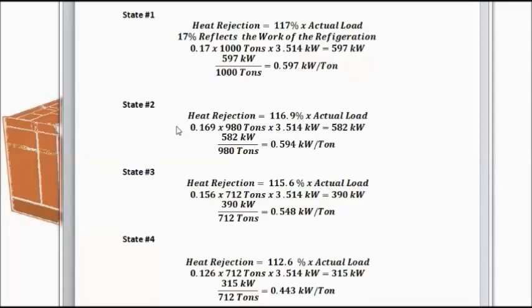And in state 2, we can make the same calculation. And we come out with 0.594 kW per ton. And since this is a variable speed chiller, we would expect a small improvement with the slight load reduction. But note that it is fairly small at this point, and maybe we should even discount it.